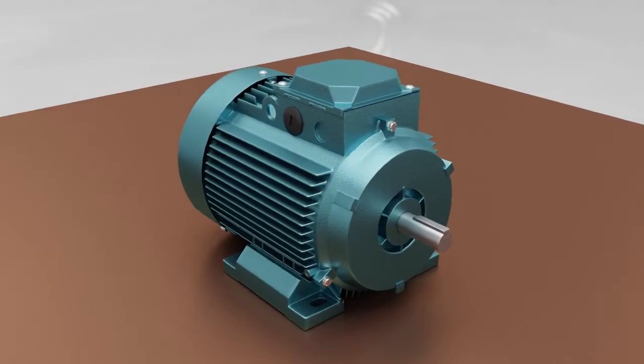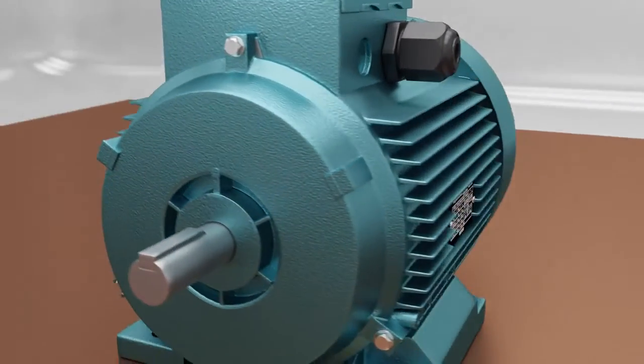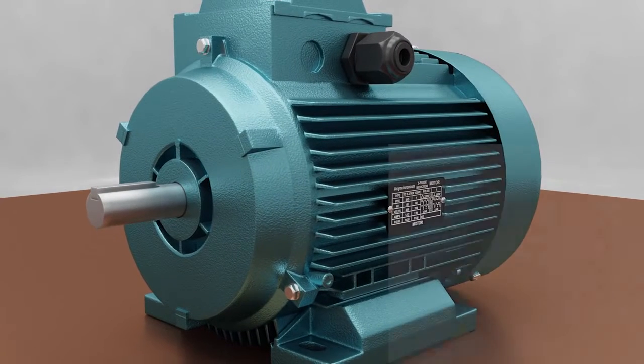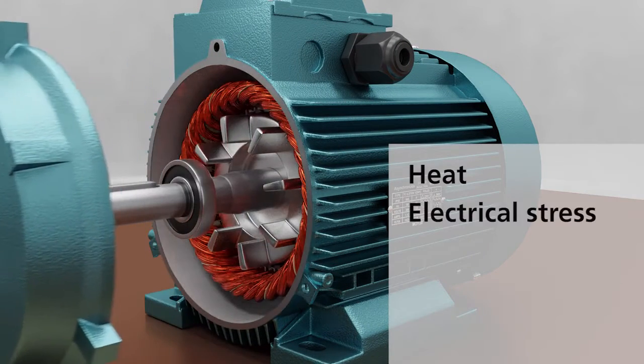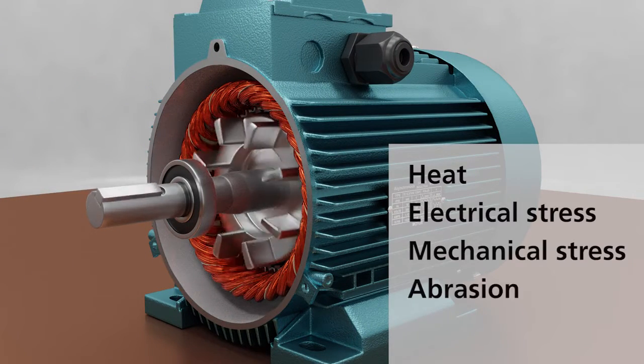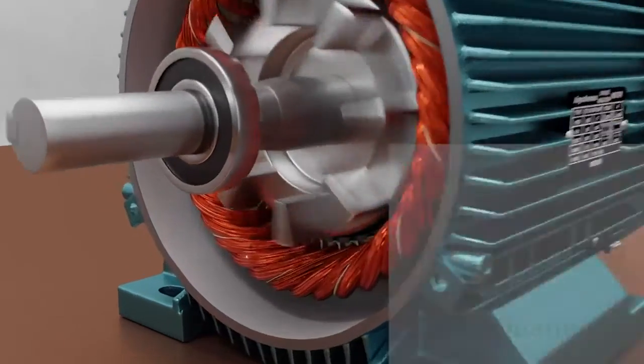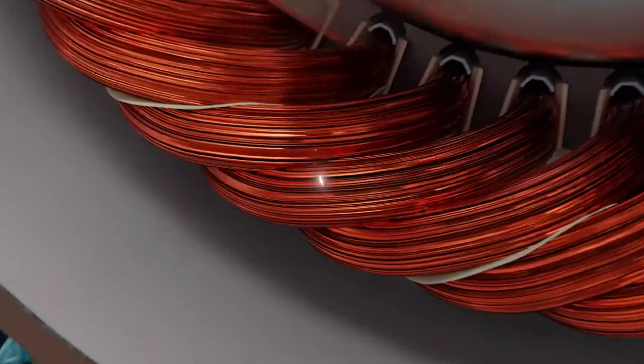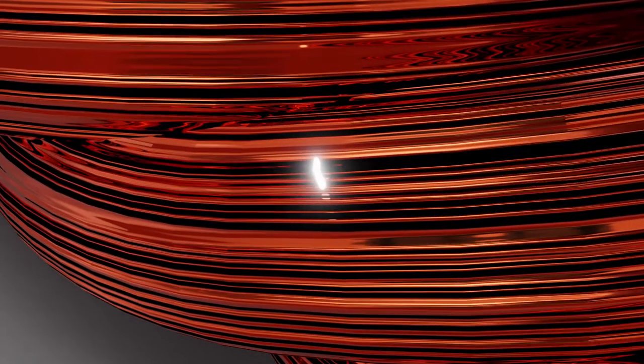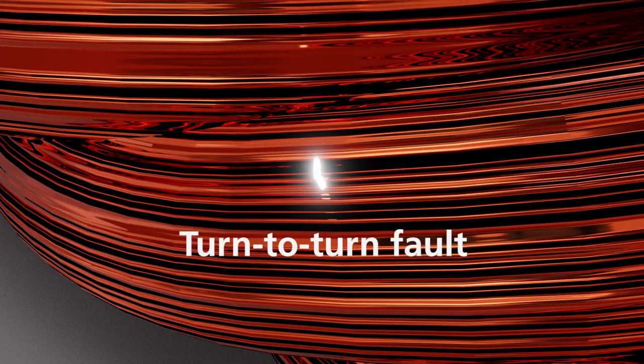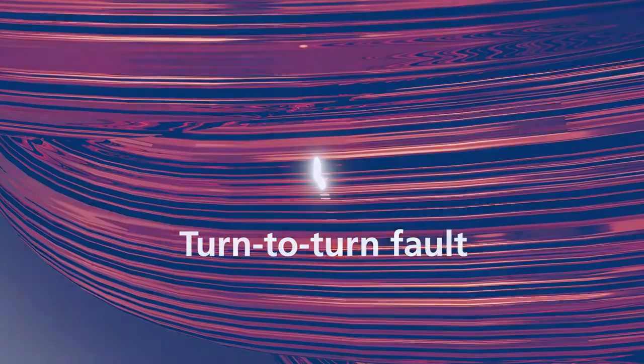The stator insulation is most prone to failure. Insulation strength degrades over time due to heat, electrical stress, mechanical stress, abrasion, and contamination. The most common insulation failure is between turns of wire that are next to each other in the same coil. This is called a turn-to-turn fault.